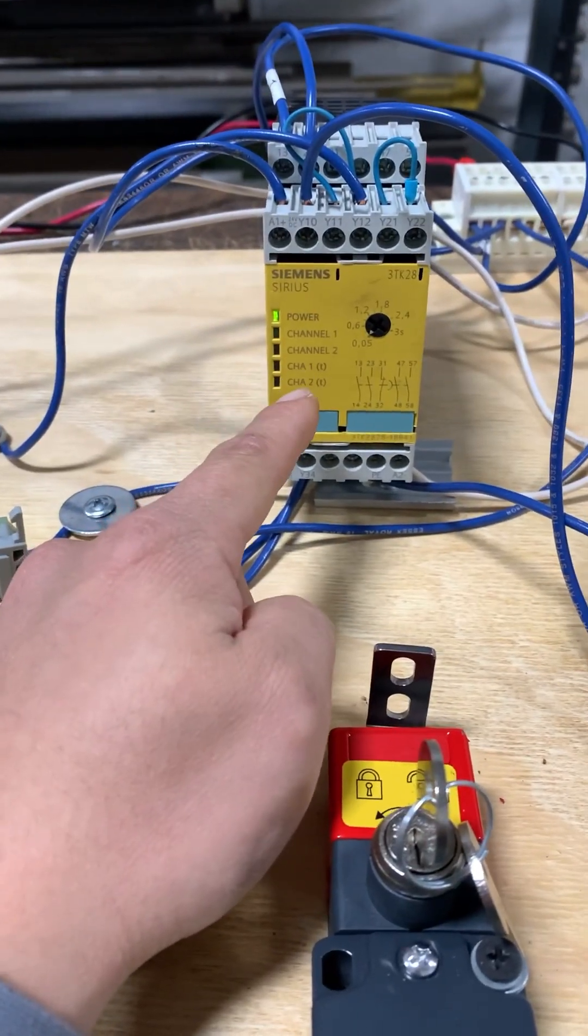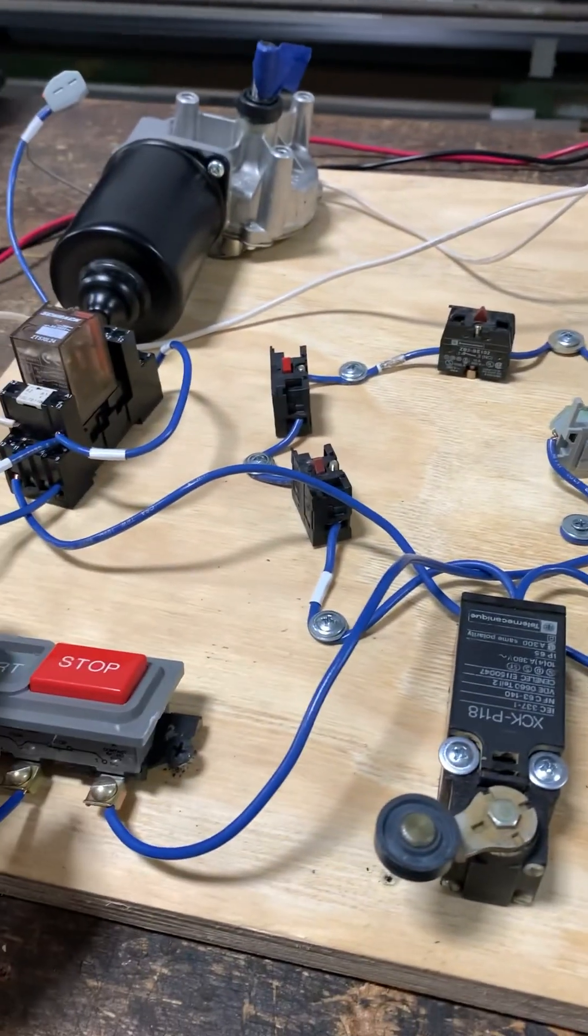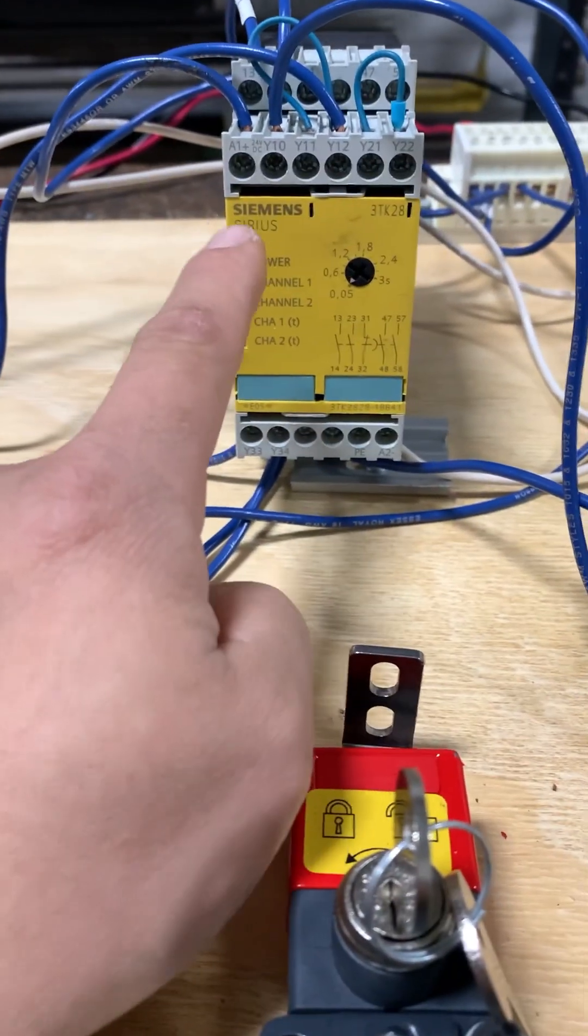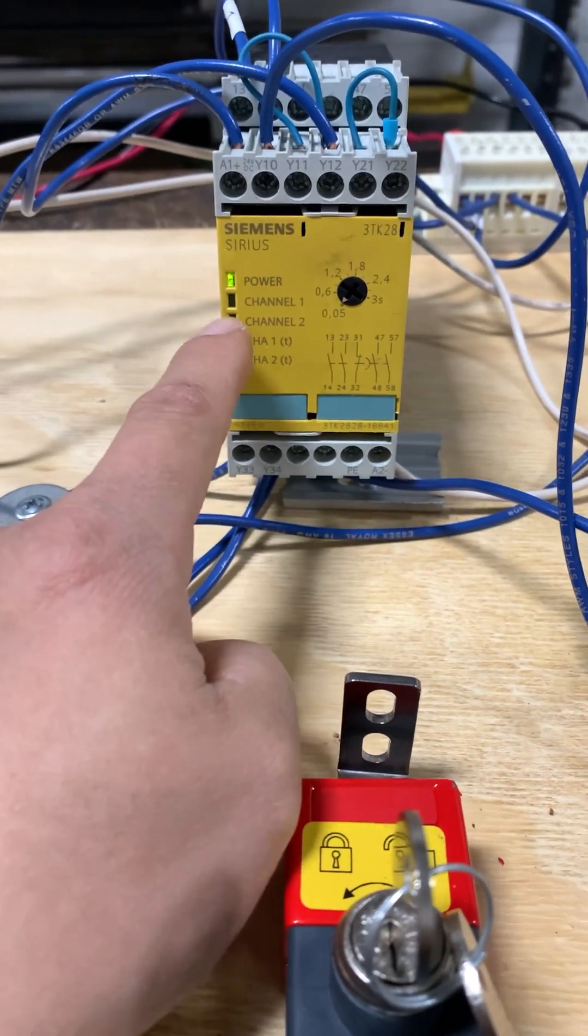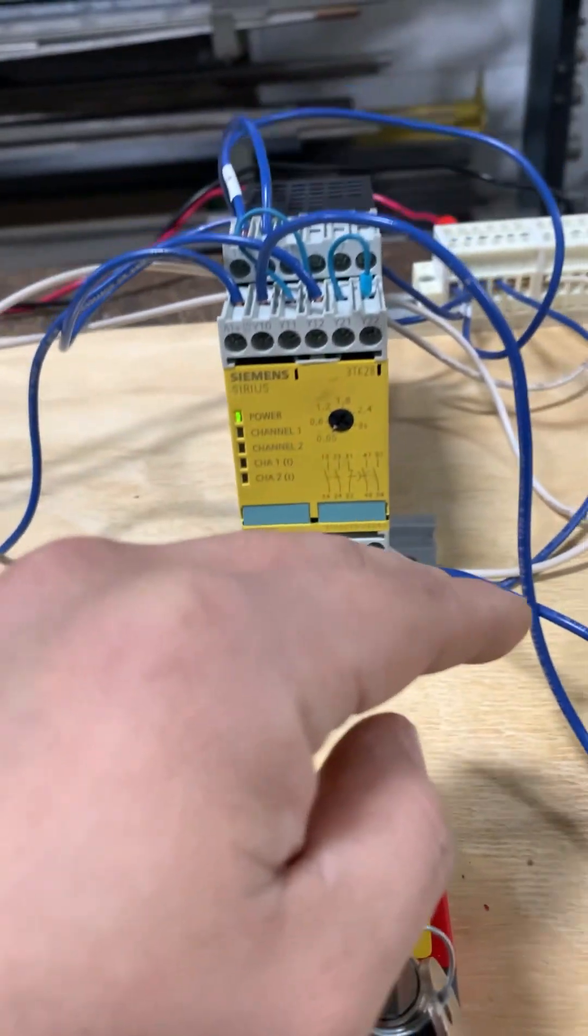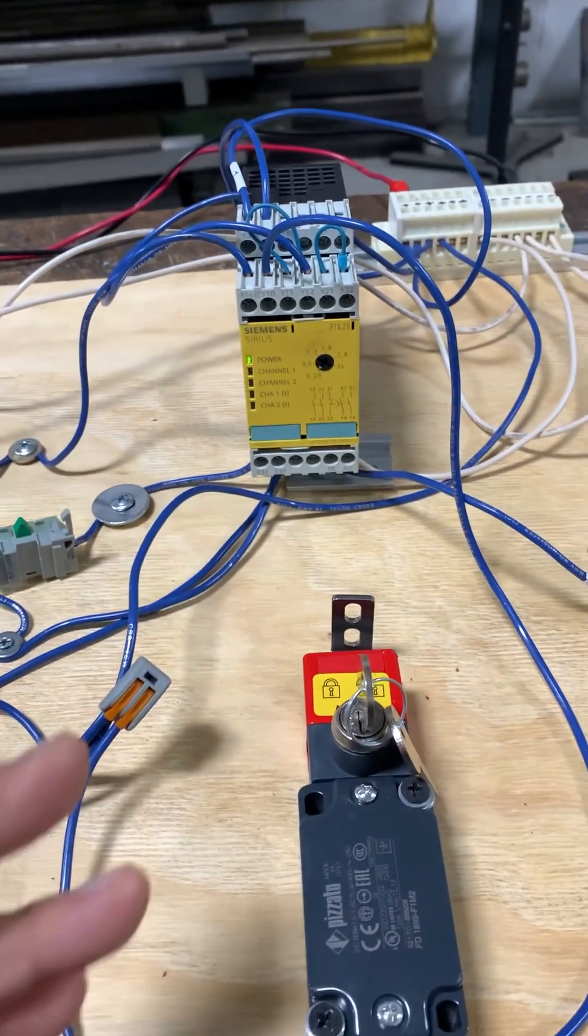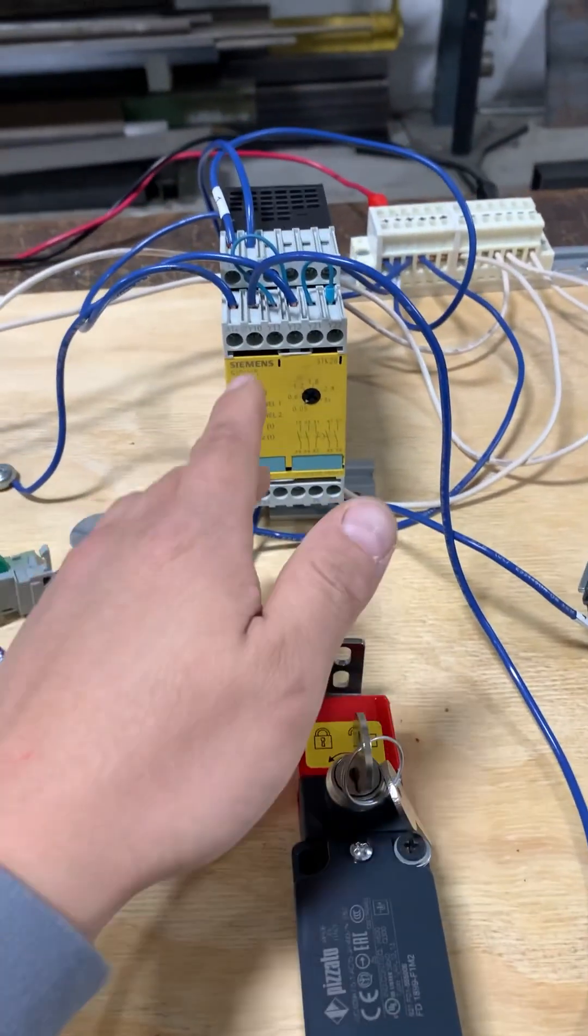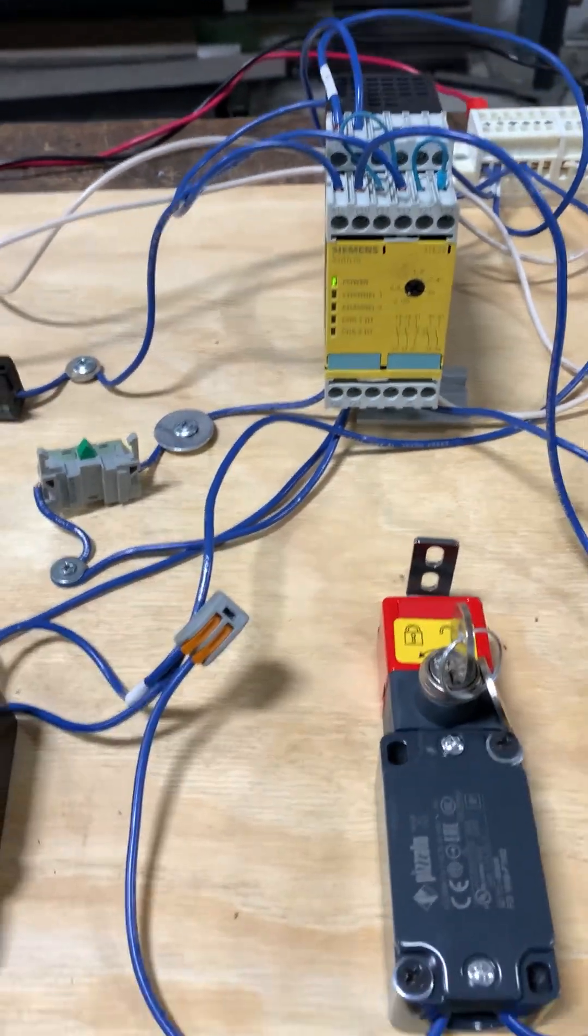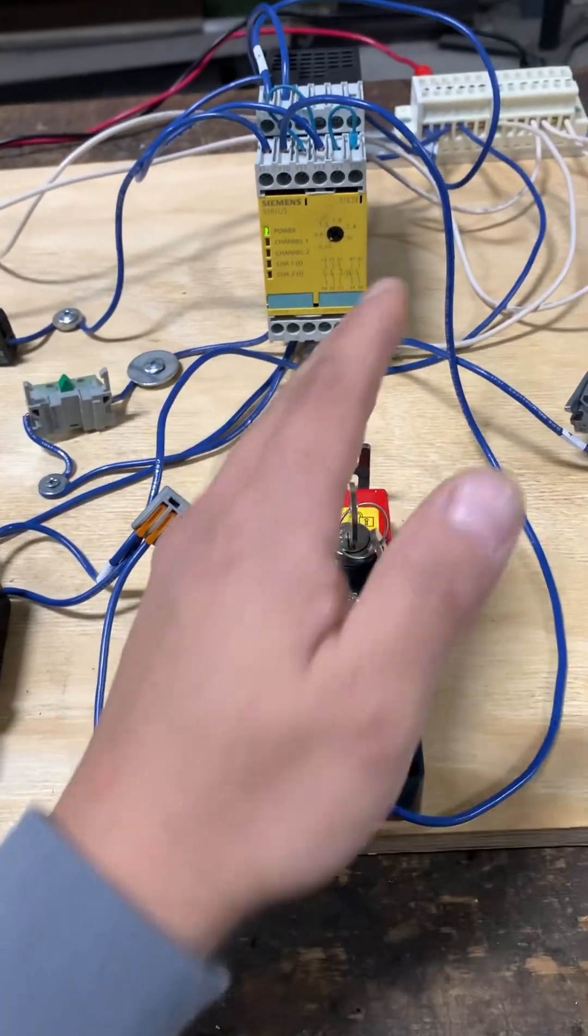So if you're ever having a problem with no control power to your machine, go ahead and open up your cabinet and take a peek at your safety relay. Make sure that all your channels are made and your safety relay is ready to go. And if it's not, then you just pull out the schematic and look at the safety circuit. So in this case here, this is my safety circuit.